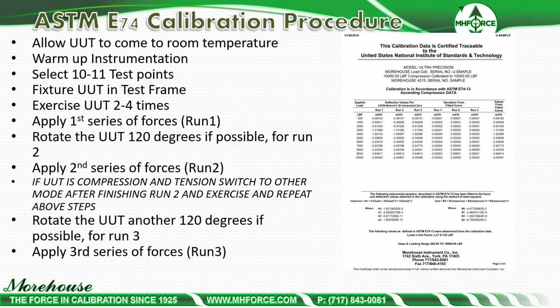Allow the UUT to come to room temperature, often a day or more of saturation in the lab. Warm up instrumentation. Normally, if you're going to power it on, 30 minutes is enough. Select 10 to 11 points. In this example, we have 11, starting with 200. Fixture the UUT in the test frame. Exercise it 2 to 4 times. Then apply your first series of forces.